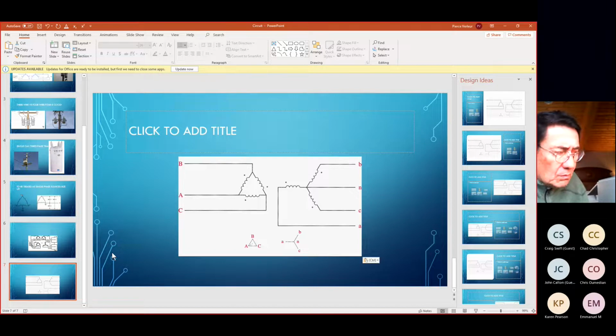So when you have a balanced Y secondary with center tap ground, you don't need to add anything else from the standpoint of power filtering to protect the drive. The capacitors will be happy, the diodes will be balanced, they will be happy, and we can move on. However, there are other things that we recommend because of other issues in the power supply, even if you have this configuration on your power pole.